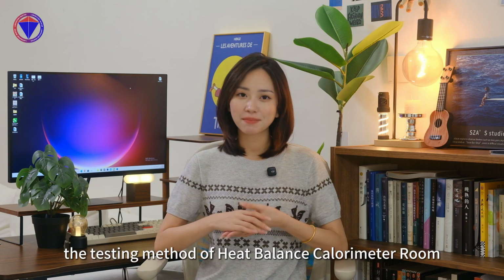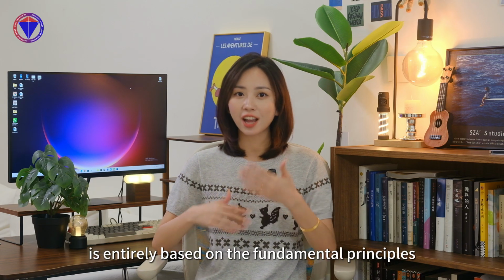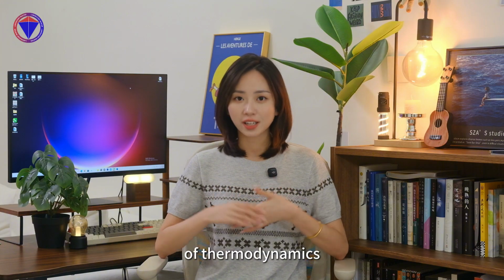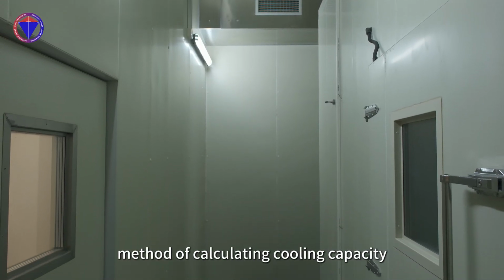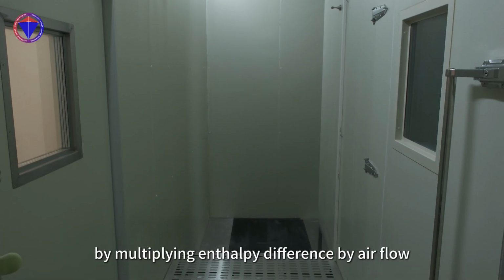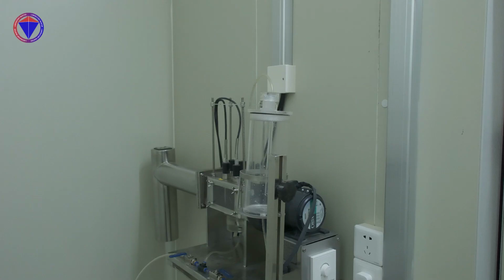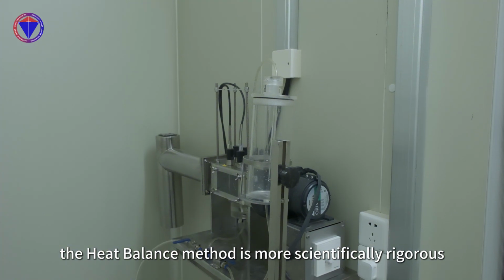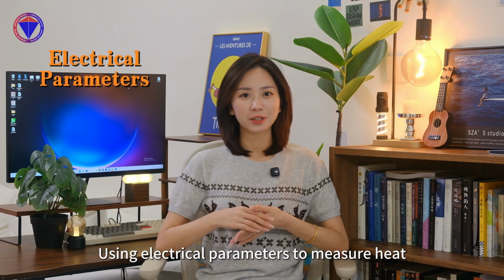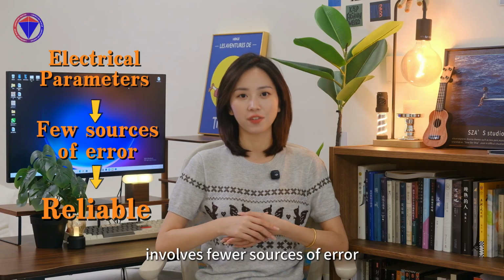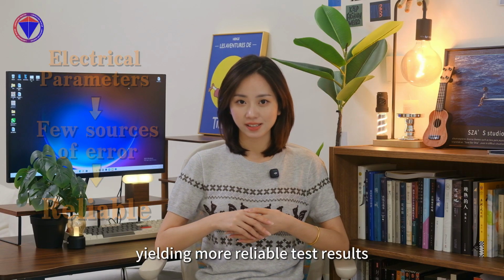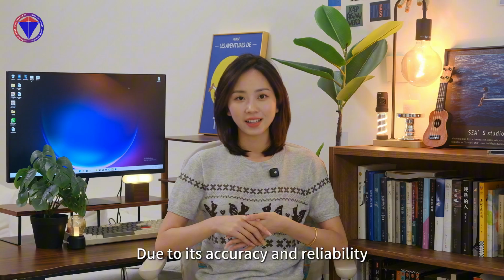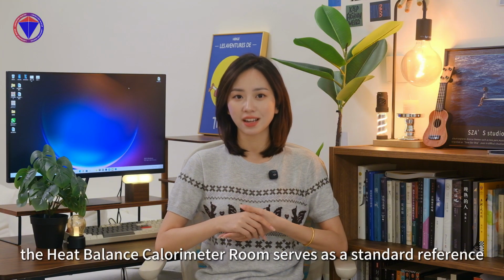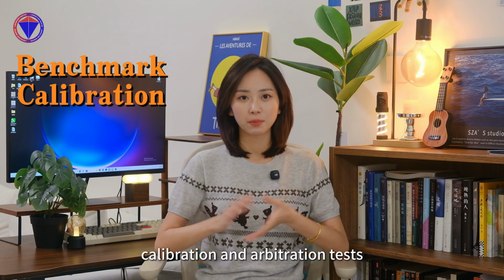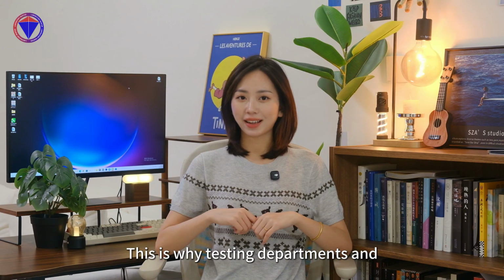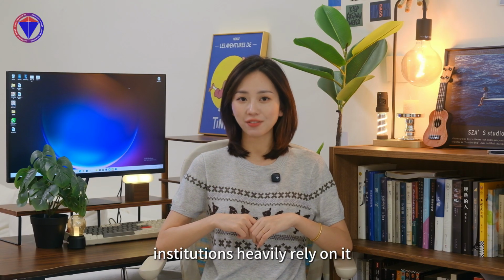In summary, the testing method of the Heat Balance Calorimeter Room is entirely based on the fundamental principles of thermodynamics, compared to the enthalpy difference lab's method of calculating cooling capacity by multiplying enthalpy difference by airflow. The heat balance method is more scientifically rigorous in principle. Using electrical parameters to measure heat involves fewer sources of error, yielding more reliable test results. Due to its accuracy and reliability, the Heat Balance Calorimeter Room serves as a standard reference, widely used for benchmark calibration and arbitration tests. This is why testing departments and institutions heavily rely on it.